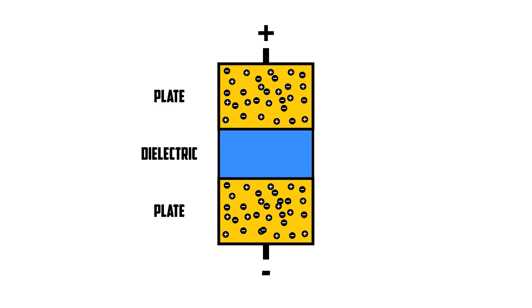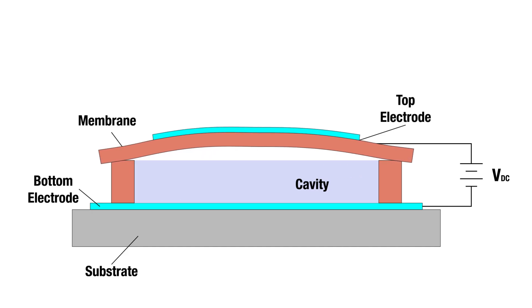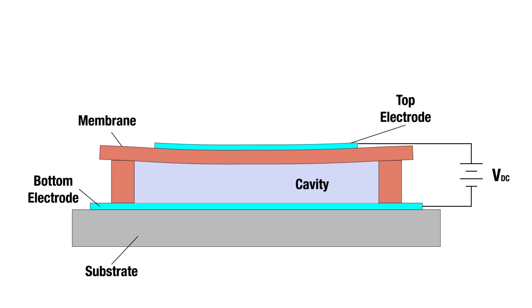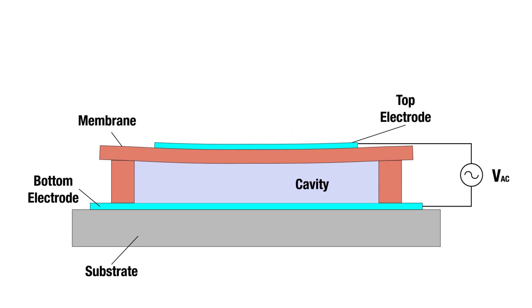The other type of transducer is capacitive. Capacitors have two conductive plates separated by a dielectric material. When connected to power, one plate gains electrons becoming negatively charged, while the second plate loses electrons becoming positively charged. In a capacitive transducer, one plate or electrode sits on a dielectric membrane suspended above a cavity in its silicon substrate, which acts as the second electrode. When current is applied, the electrodes become charged and the top plate is attracted to or repelled by the lower plate, moving the membrane. Applying an alternating current causes this to happen quickly, making the membrane vibrate and generate ultrasonic waves.